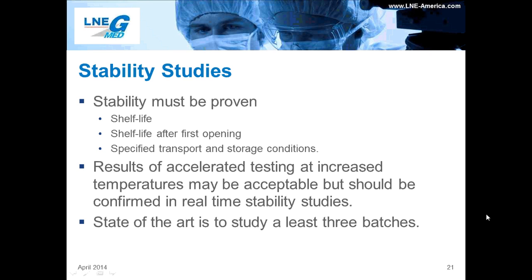Stability studies must be included in the technical documentation to support the claimed shelf life of the product. This should not only include the shelf life from date of manufacture, but also the shelf life once the product has been opened. It must be proven that the performance and the microbiological state of the whole kit is still suitable at the end of shelf life. Stability also must take into consideration any specified transport or storage conditions. For instance, in the case of an assay run on instruments, this would include onboard storage of the product if it's included in the product claim.